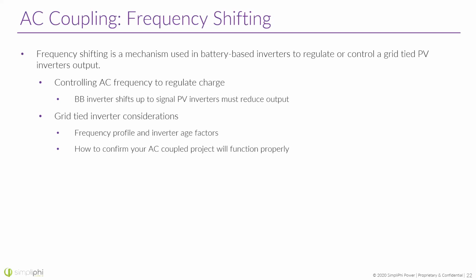And then, Nathan, that brings us into a question we're getting: how much PV can we add to an AC coupled system? Our batteries are rated at a C/2 rating. The easiest way to think about this is that the batteries could charge from 0 to 100% in 2 hours. You don't want to be charging faster than that. So for our 3.87 kilowatt hour batteries, we're looking at about 1.9 kilowatts per battery. If we charge faster than that, we can damage the batteries. And if you had, let's say, 3 of these batteries, you're looking at about 5.7, 5.6 kilowatts of power. We have some examples where we can do this, but you want to make sure that you're sizing your system appropriately when you're AC coupling to string inverters or microinverters.